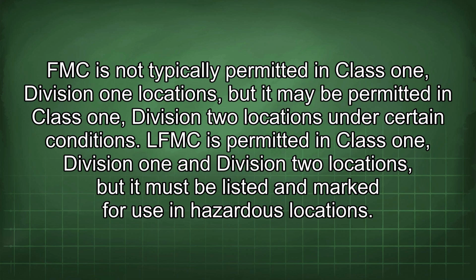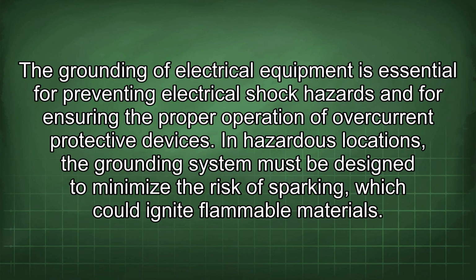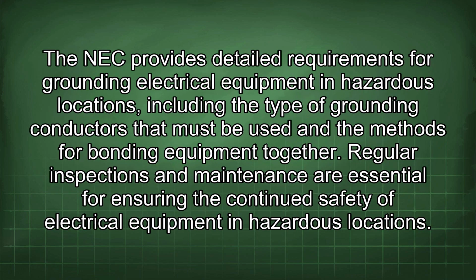The grounding of electrical equipment is essential for preventing electrical shock hazards and for ensuring the proper operation of overcurrent protective devices. In hazardous locations, the grounding system must be designed to minimize the risk of sparking, which could ignite flammable materials. The NEC provides detailed requirements for grounding electrical equipment in hazardous locations, including the type of grounding conductors that must be used and the methods for bonding equipment together.